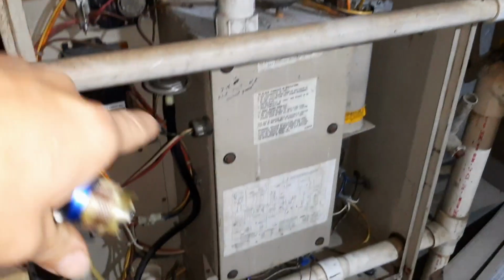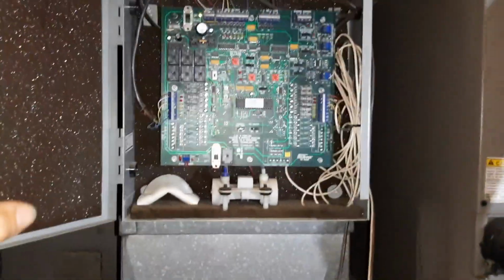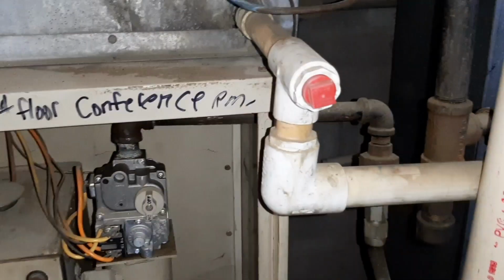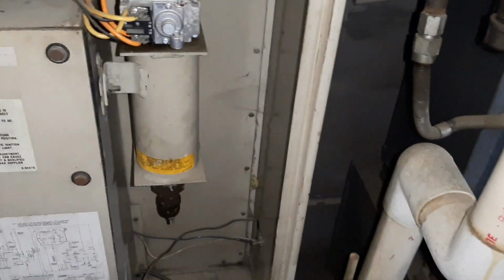So we've got some stuff labeled wrong. This is my second floor unit. It looks like here it's got the zone control on it, an old air boss. I've got one damper there that feeds over into that room. You can see how they did the duct here. I don't know how correct all this is, but this feeds the other side of the second floor. So I just got two dampers. Everything else feeds down. We're going to verify those dampers are open. This is labeled second floor, but it's not, because my duct goes down.